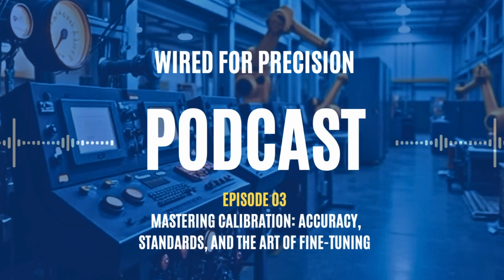4. Labeling and documentation. After calibration, the instrument should be labeled with the calibration date, due date, who performed it, and whether it passed or failed. Good documentation includes instrument tag number, reference standard used, environmental conditions, results, as found or as left, tolerances.